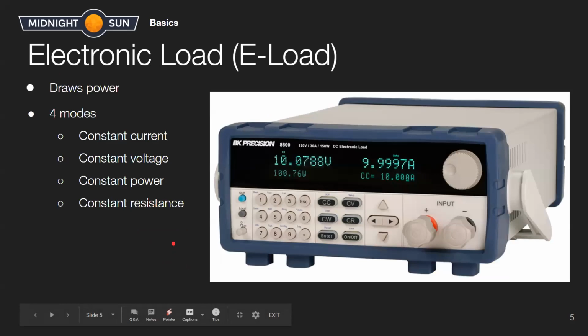So electronic loads, sometimes called E-loads, just have two terminals and they just draw current depending on the mode that has been set. So there are 4 modes: constant current mode, where you just tell it how much current to draw and it'll draw that current. Constant voltage mode, where it will draw current until the voltage at its terminals is equal to the voltage that's set. Constant power, where it will just draw power until the voltage across its terminals times the current that it's drawing reaches the set threshold. And then constant resistance, this basically just acts like a programmable resistor.